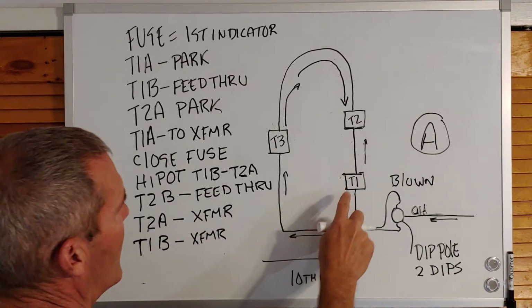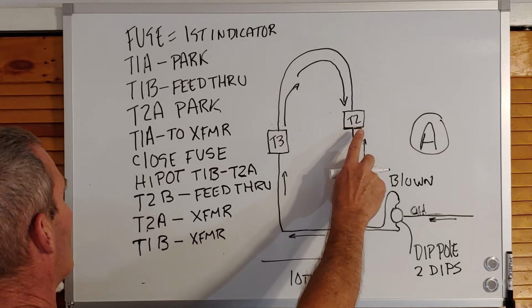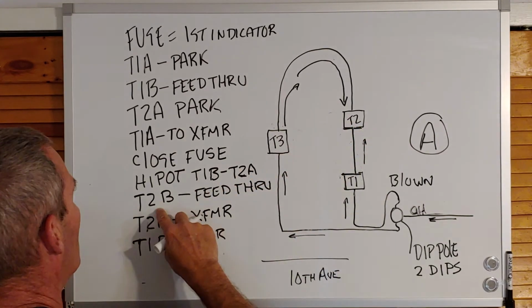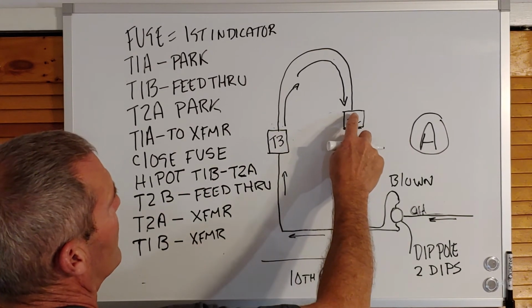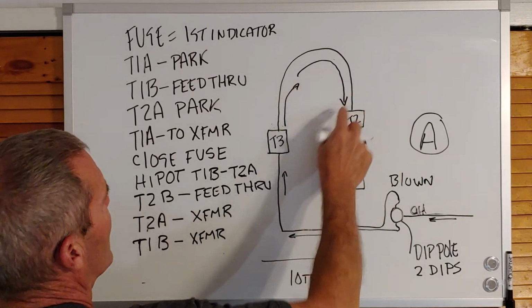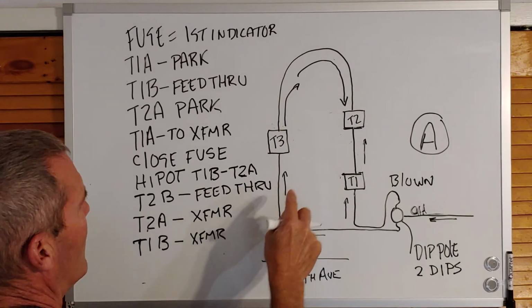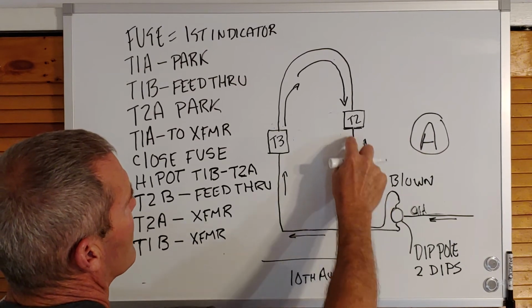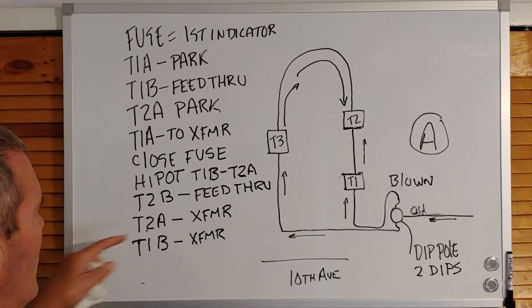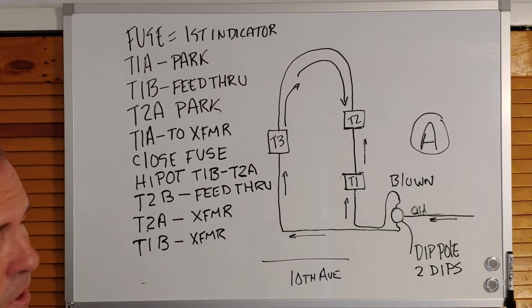Now I've energized the cable up to this point right here. The T2B outbound is isolated because I have it on the feed-through, and T2A is on the transformer right there, so I'm able to energize the transformer.